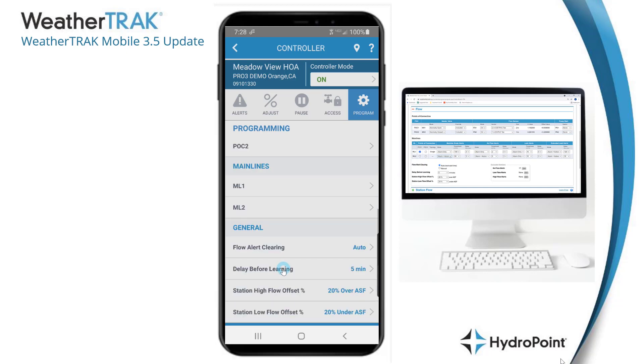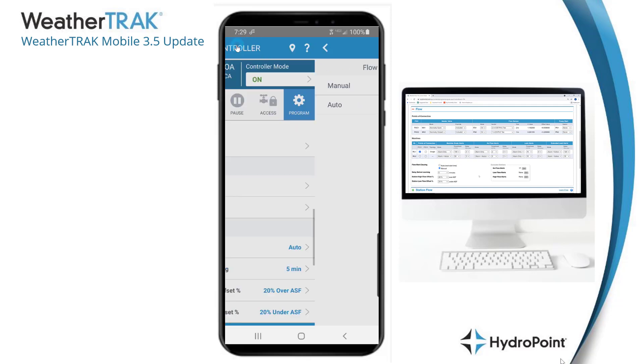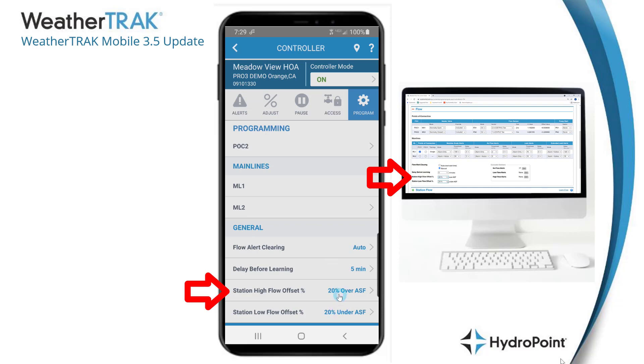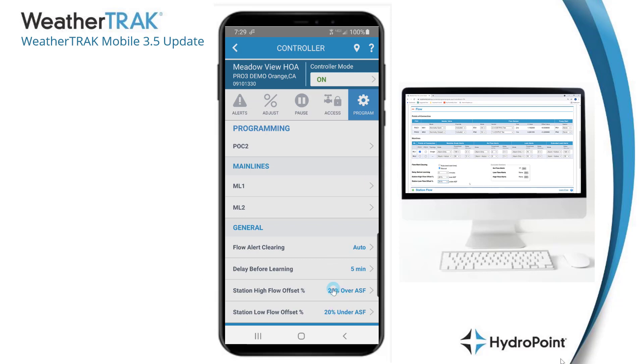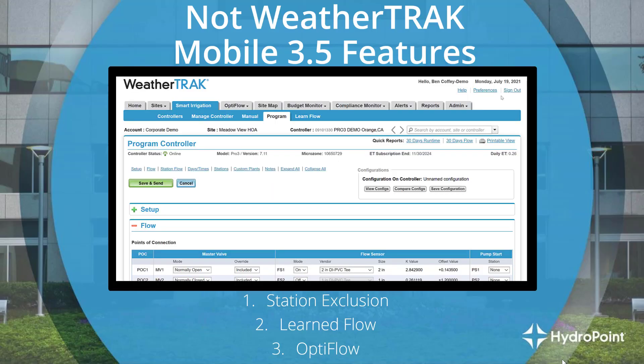Once main line programming is complete, scroll down for a few last general flow settings. First, flow alert clearing — if you want flow alerts to clear and retest at the program start time, set that to auto; or you can program it to require manual clearing. Then we have the delay before learning and the station high flow and low flow offsets that are used to create the station high flow and low flow alert thresholds.